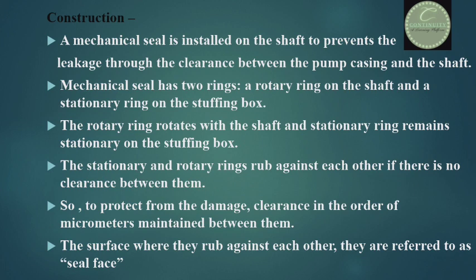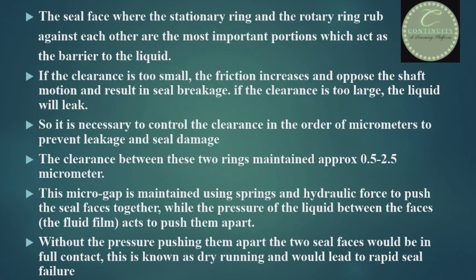The rotary ring rotates with the shaft while the stationary ring remains stationary on the stuffing box. If there is no clearance between them, they rub against each other and damage themselves. So to protect from damage, a clearance is maintained between them in the order of micrometers.